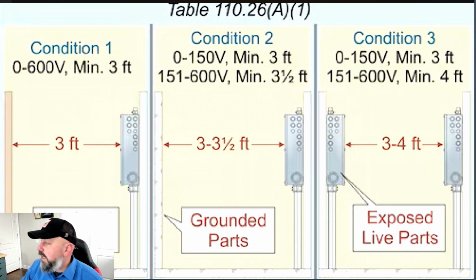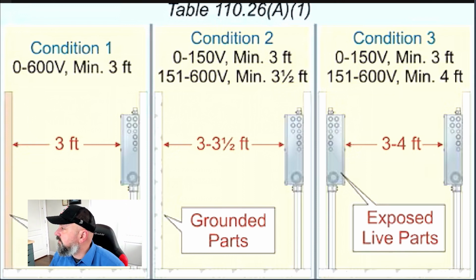So here we go. And let me just move my floating head so you can see this. It doesn't really help. We'll just do it like that. I'm just floating here. Condition 1, 0 to 600 volt, 3 feet. So that's wood, that's drywall, all those materials. You only have to have 3 feet if it's across from there. Condition 2, grounded material. So they're talking about the moisture and everything that's in concrete that could be grounded. So concrete walls, block walls, tile walls, you're going to have to go 3 feet to 3 feet 6 inches. So right here, 0 to 150 volt, 3 feet, 151 volt to 600 volt, minimum 3.5 feet.